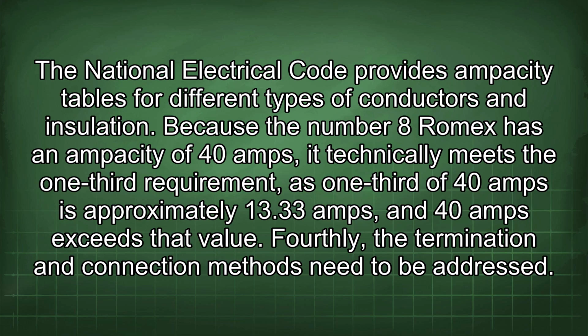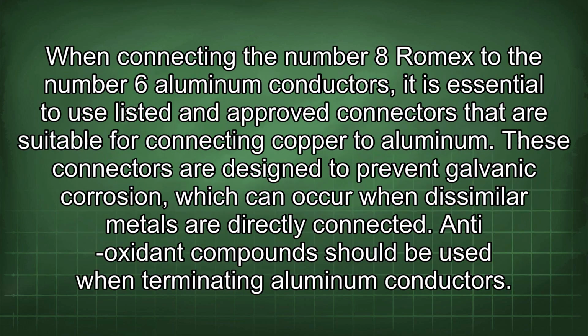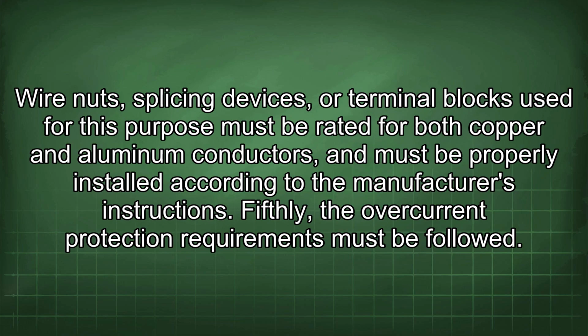Fourthly, the termination and connection methods need to be addressed. When connecting the number 8 Romex to the number 6 aluminum conductors, it is essential to use listed and approved connectors that are suitable for connecting copper to aluminum. These connectors are designed to prevent galvanic corrosion, which can occur when dissimilar metals are directly connected. Antioxidant compounds should be used when terminating aluminum conductors. Wire nuts, splicing devices, or terminal blocks used for this purpose must be rated for both copper and aluminum conductors and must be properly installed according to the manufacturer's instructions.